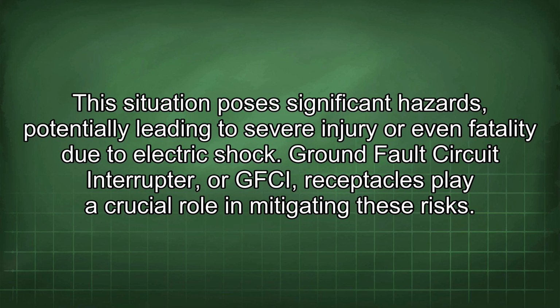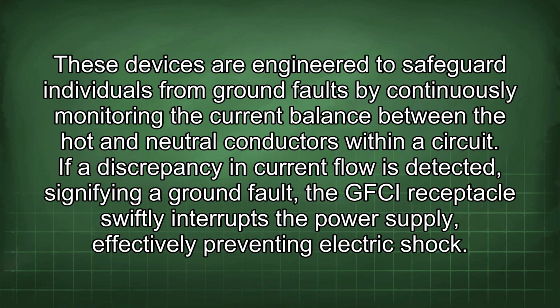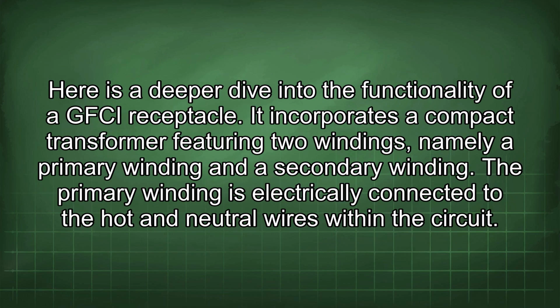Ground fault circuit interrupter, or GFCI, receptacles play a crucial role in mitigating these risks. These devices are engineered to safeguard individuals from ground faults by continuously monitoring the current balance between the hot and neutral conductors within a circuit. If a discrepancy in current flow is detected, signifying a ground fault, the GFCI receptacle swiftly interrupts the power supply, effectively preventing electric shock. Here is a deeper dive into the functionality of a GFCI receptacle.